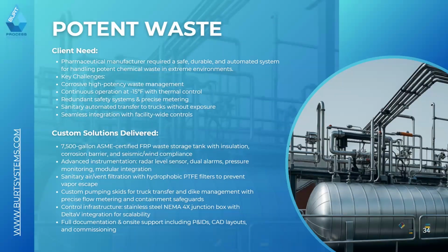These types of systems are treated a little bit differently. These can either be outside or inside large storage tanks. Radioactive tracers can fall into this category as well. That's not as common today as it used to be. You see that a little bit more in the veterinary waste streams where people have isotopes that need to be allowed to go through their half-life. These have different venting requirements. These typically have an isolated cam lock monitored panel system so that the operators who are hooking this up to have this transferred off site can monitor the tank level.